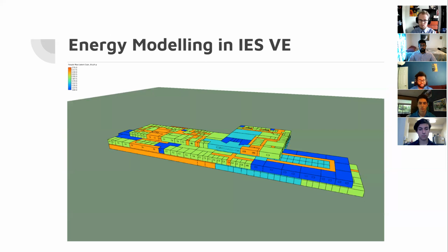Each room is separated into different thermal templates, such as kitchen, office, corridors, restrooms, and theater. These templates dictate the room's internal gains, such as lighting and equipment, its cooling and heating set points, and required airflow. These templates allow us to generate a simulation report that takes the specific data set we need for the equipment selection, such as VAV boxes and air handling units.